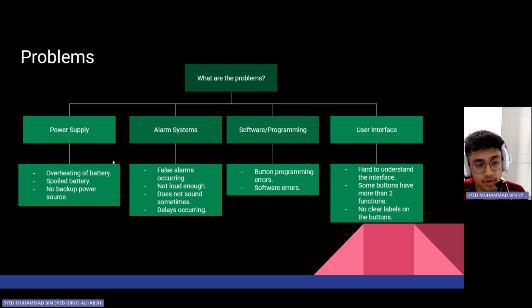When the battery of the infusion pump overheats or is spoiled, the whole infusion pump will stop functioning, and this will stop the infusion of the liquid medication into the patient. If the patient is in a critical condition, this may affect the patient and actually threaten their health. The fact that there is no backup power source also affects this, as if the power source is spoiled or is overheated, there'll be no backup power source to help continue the flow of the liquid, which, as I said, will affect the health of the patient.